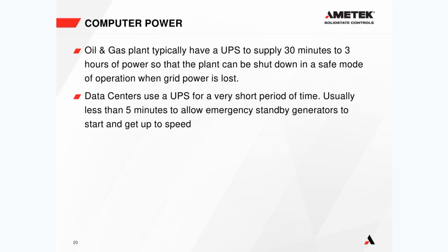So for an oil and gas plant, typically they will have a UPS to supply roughly 30 minutes to up to 3 hours of power so that the plant can be shut down in a safe mode of operation when grid power is lost. So from the control room, they can start a standard shutdown procedure that shuts down the process in a controlled way. That means equipment's not going to be damaged, people are not going to be harmed, everything is done in a very controlled way. Okay, so the UPS will last between 30 minutes to 3 hours. Hopefully the grid will come back on again before you get to that end of time. But that's usually what a UPS in the petrochemical industry lasts for.